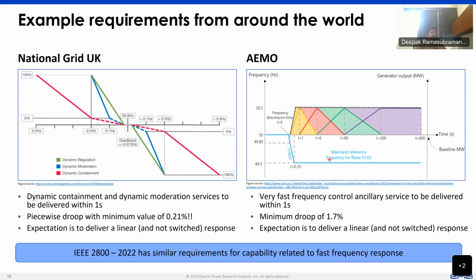There are comparable requirements in Australia that have also come through their market ancillary services product, wherein you can have very fast frequency control ancillary service delivered within 1 second with a minimum droop of 1.7%. And again, the expectation is to deliver it in a linear manner and not a switched manner. IEEE 2800-2022 has similar requirements for capability related to fast frequency response, although the time mentioned will have to be read carefully, but there is the capability to exceed the requirements in the standard and provide fast frequency response. And a lot of this response is provided at the inverter level and not necessarily at the plant level.